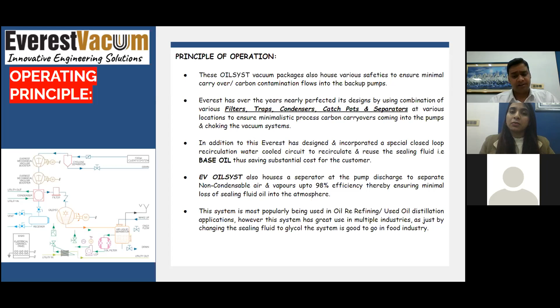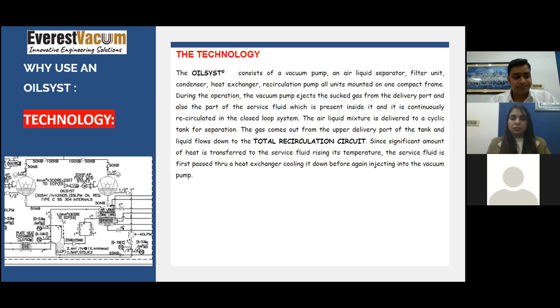So, as discussed earlier, why use an OILSYST? Because of the provisions we use, the oil system conserves the same sealant fluid, giving you recycling of it. It reutilizes the filters and other components, helps stop carryover inside the pumps, and gives better suction capacity with oil circulation. It gives a good vacuum level compared to other liquid ring or oil vane pumps, offering a vacuum level of around 20 torr under blank conditions.